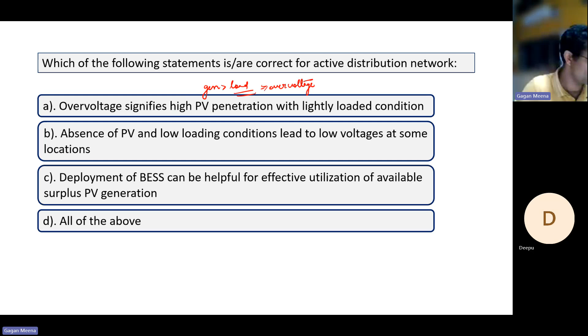So here we have to see: over voltage signifies high PV penetration with lightly loaded condition. Yes, it is correct, because here generation is much more than the load, and that's why it results in over voltage. And if PV is not there and load is also less—absence of PV and low loading—if load were more than generation, then there would be low voltage. But here PV is also not there and load is also less, so we cannot say anything about the voltage here, because we don't know the relation between generation and load.